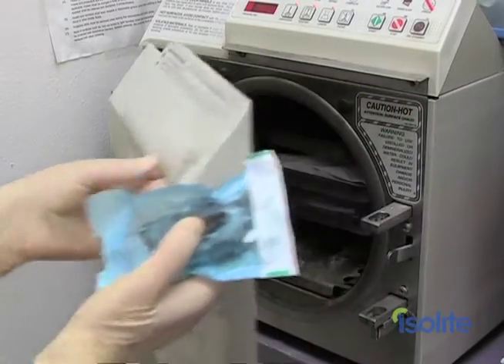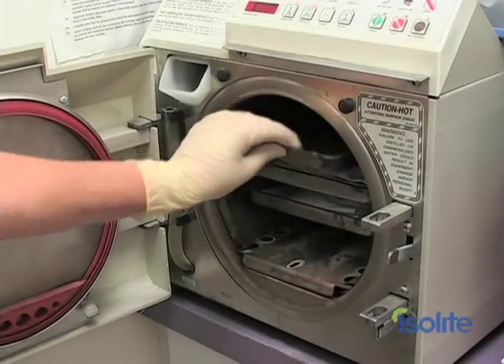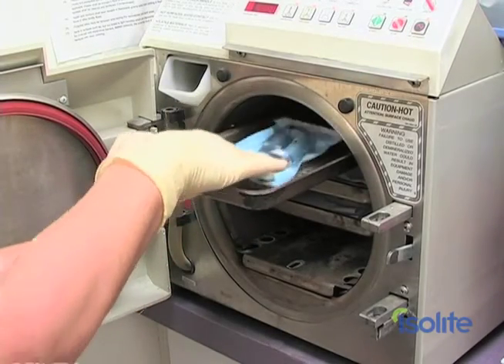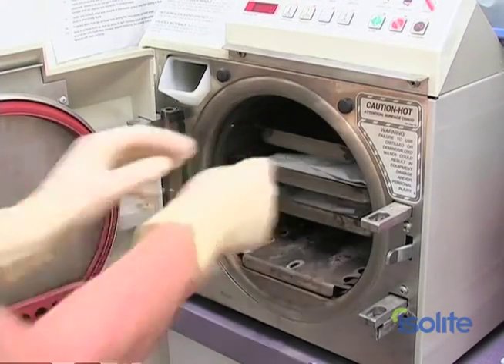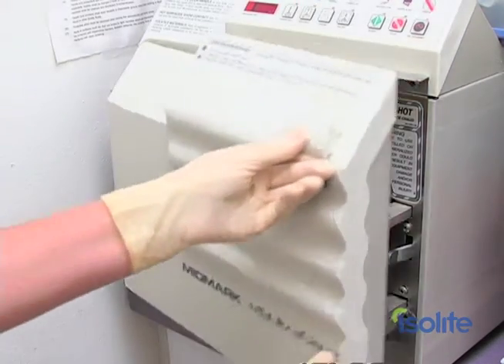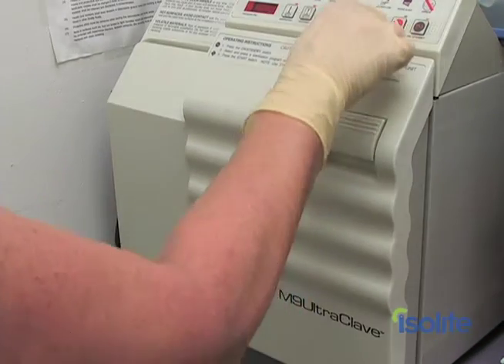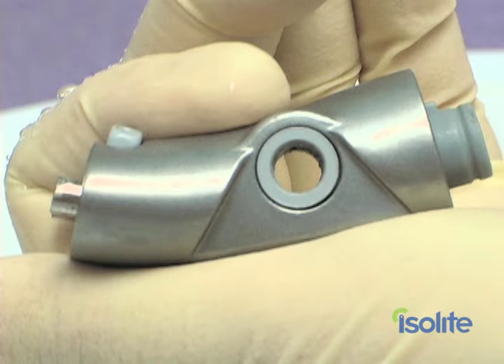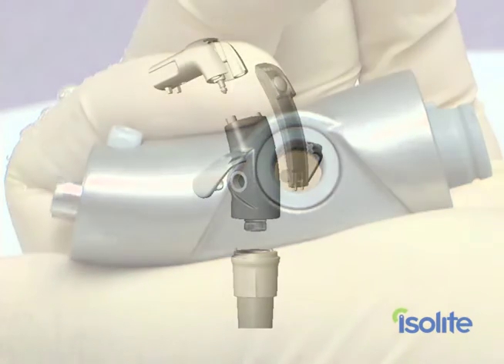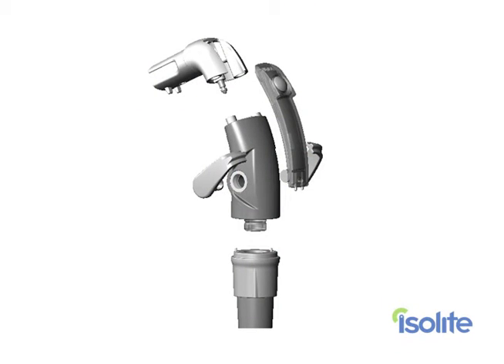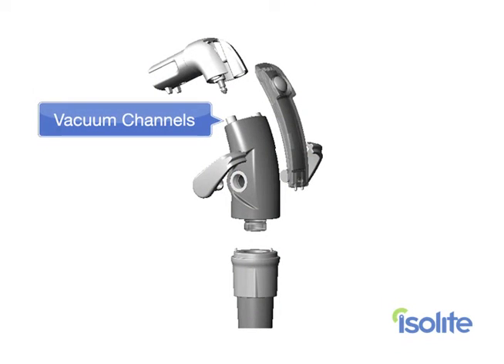Autoclave the titanium main housing. Do not cold sterilize. If your autoclave has a full dry cycle, use that setting for cleaning of the main housing. It is very important that the unit is completely dry prior to use. You can use your high speed to blow dry the vacuum channels and to blow dry any connections at the base of the main housing assembly.